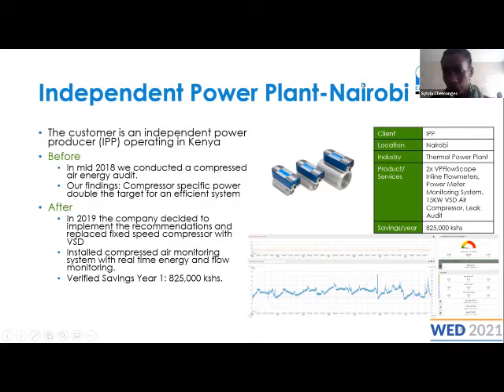Then from there, we saw the energy consumption and figured out ways in which we can minimize it. After carrying out the energy audit, we recommended that the client fix their leaks, incorporate a VSD compressor because they were using fixed speed compressors, and carry out continuous monitoring of their system. From that, we recommended a 15 kilowatt VSD compressor, which was installed in 2019.